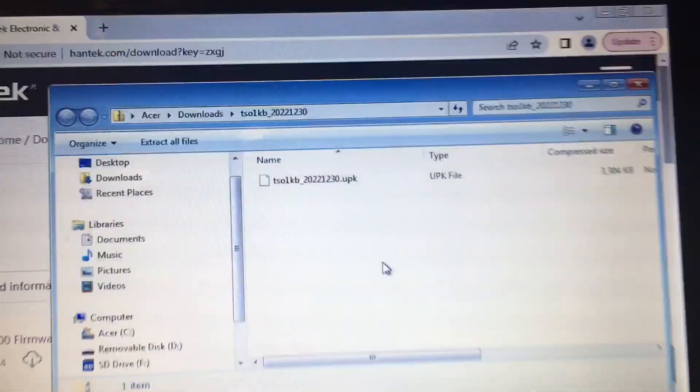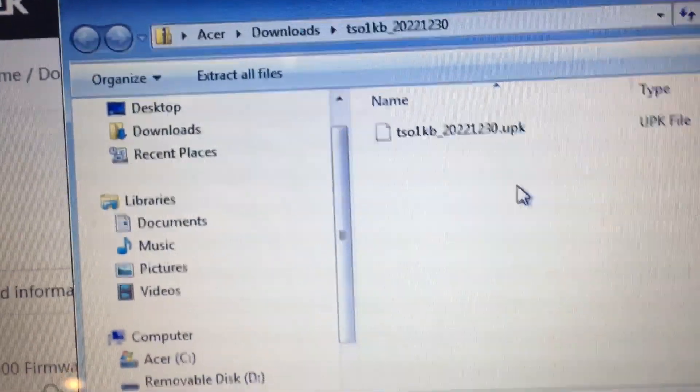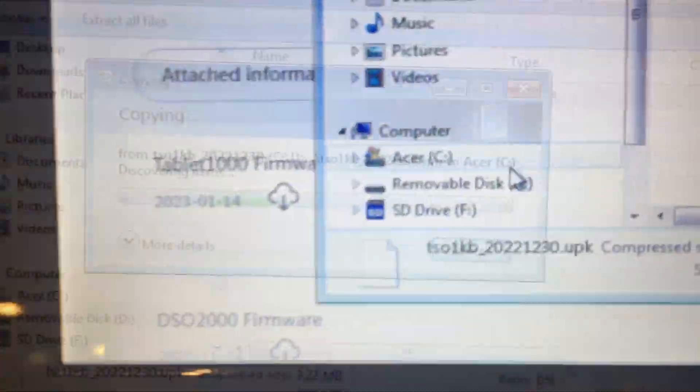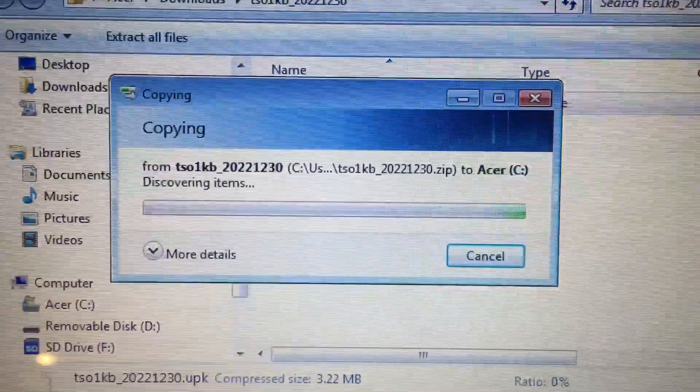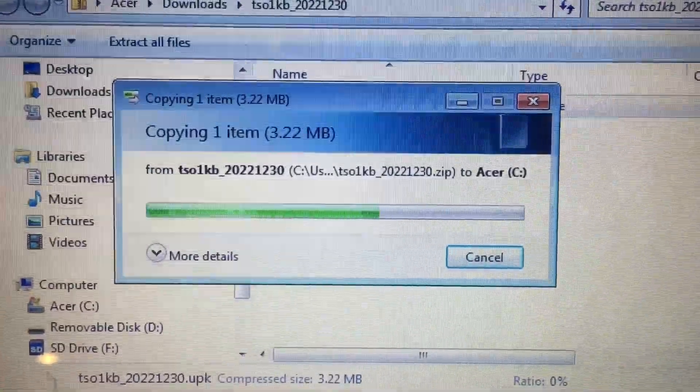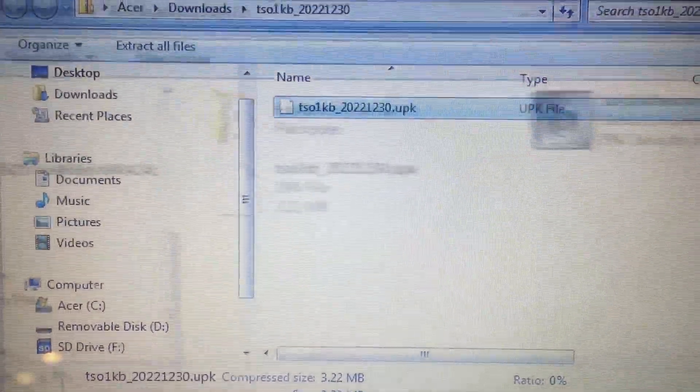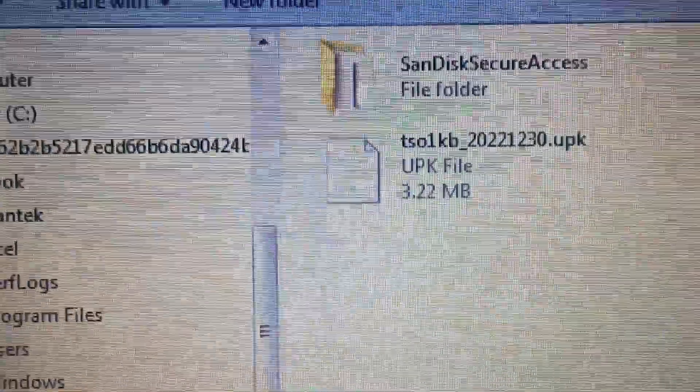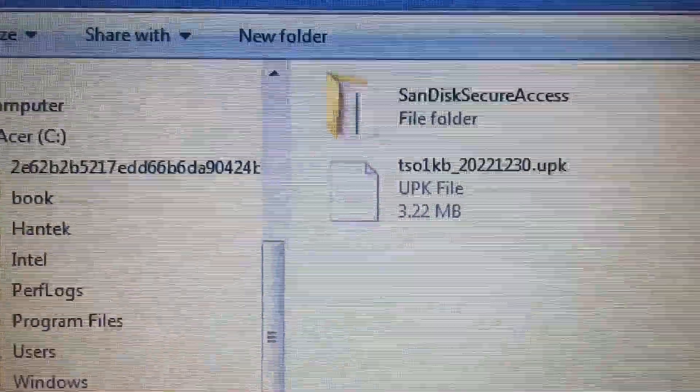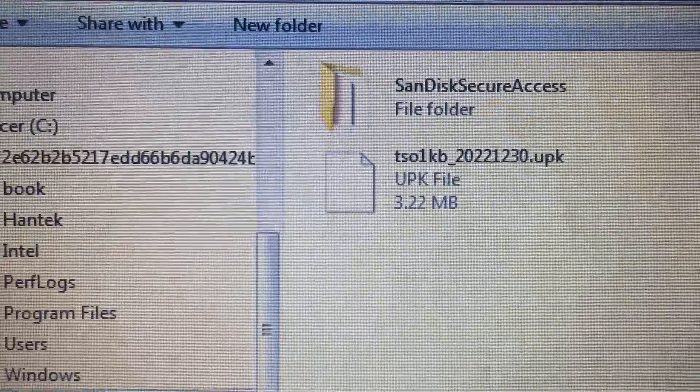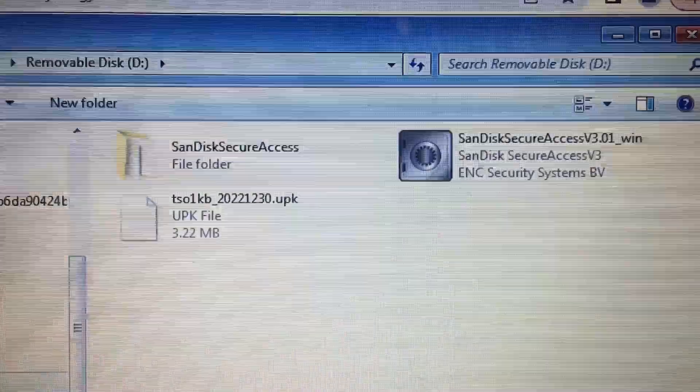So there it is on my hard drive on my computer. I'm just going to transfer it. You can see my little thumb drive there. I'm just going to transfer it over to the thumb drive. So now I have the upgrade package file. You can see the name of it there on the thumb drive. I'm now going to take the thumb drive to the scope.